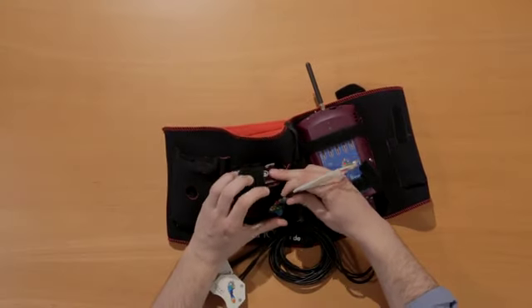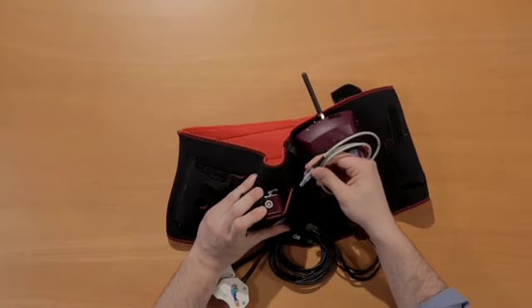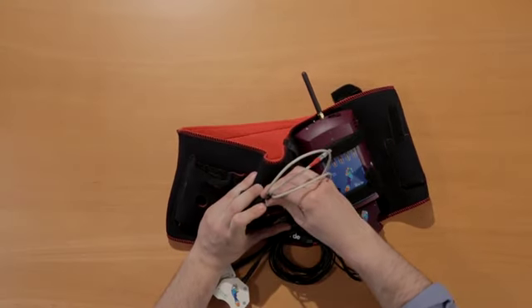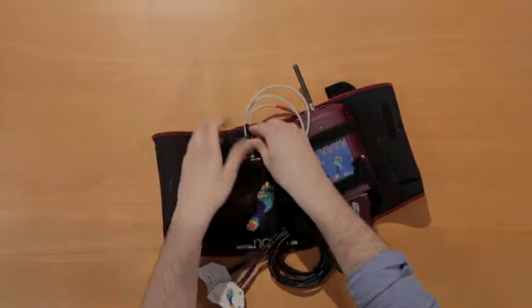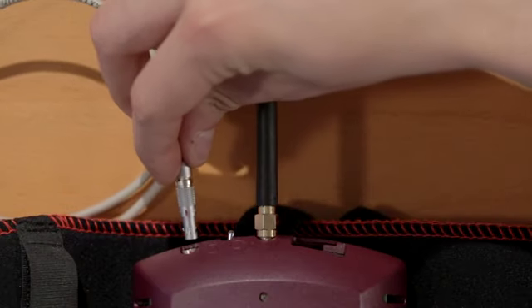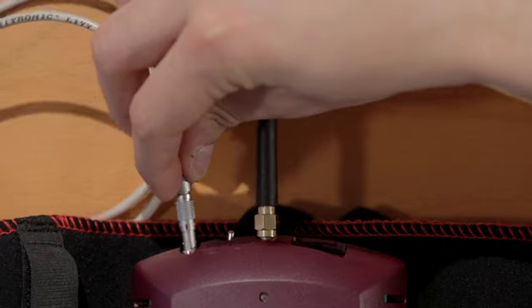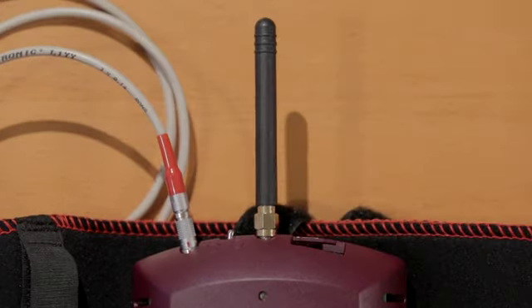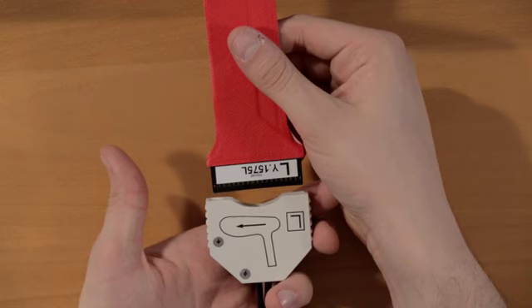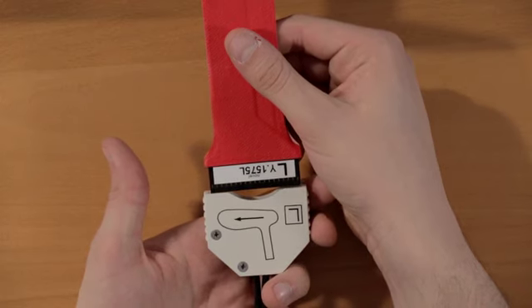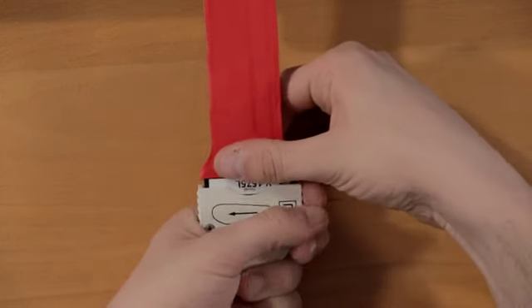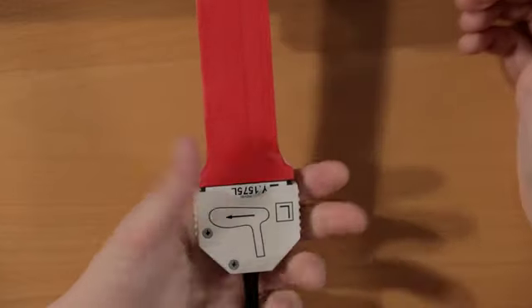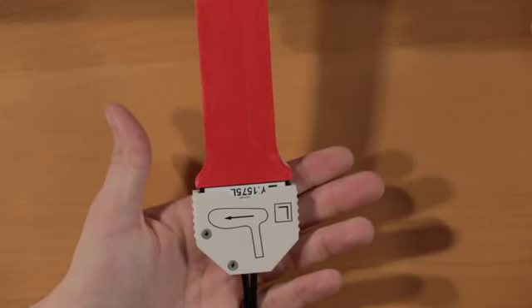Step 2. Connect the pedar box to the battery by means of the battery cable. Ensure that the red dot on the device is in line with the red dot on the cable. Connect the insole cable to the insole by connecting the L of the insole to the left side of the cable, and similarly, the R of the insole to the right side of the insole cable.